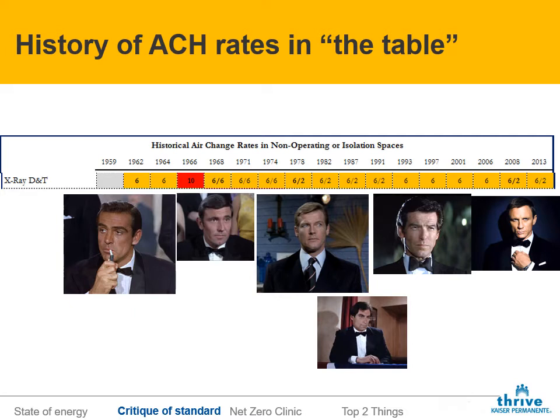We did have that one weird code cycle where it shifted up to 10 air changes, which roughly aligns to the single film appearance of George Lazenby as 007. But then for the rest of the time, we just use 6 air changes. And this is where I point out that most of the X-ray rooms we've built since Roger Moore took over as James Bond, most of the X-ray rooms we built in the last 30 years are in medical office buildings, B occupancy buildings. Or in California, we would call them non-OSHPD buildings. And now we call them imaging rooms, not X-ray rooms.